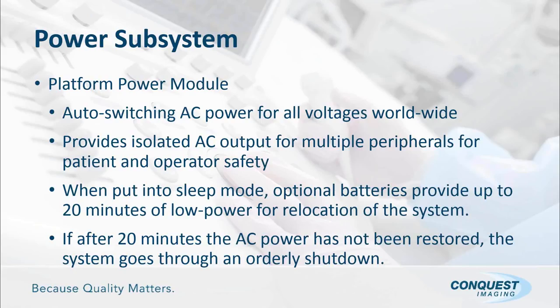that particular power. It provides an isolated AC output for multiple peripherals, and it sets up the environment that makes a safe environment for both the operator and the patients. And why do I mention that? Because it's really important that you use these isolated outputs because many of the hospitals and clinics, particularly OBGYN, bypass this mechanism by hooking up, for example, a monitor on the wall so that the mom can see her baby as they're doing the scan, and that monitor is plugged into the back of the system for video, but then plugged into the wall, the unisolated wall outlet, and that gives it an unsafe path to ground and can cause potential problems. So try to prevent that from happening if you see it occur in your hospital or clinic.